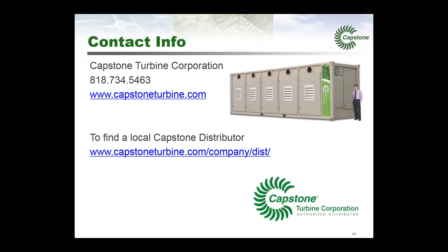So we can actually get away from demand charges in a way that some other technologies may have a harder time. Standby charges and departing load are things that I would like to see go away. For people that aren't familiar with it, if you put a megawatt of new generation at your facility, some utilities, not all, will charge you for a megawatt of departing load. So there's some fee they'll have for having once provided you essentially with that megawatt. Generally speaking, in places where we see those sorts of tariffs, it does not ruin the economics. It will just add maybe half a year to the payback. And we're working actively to try and get some tariffs out there that make a little bit more sense in that respect.